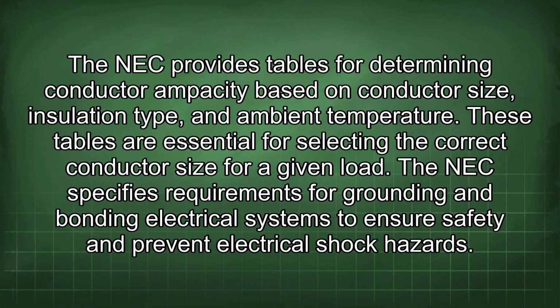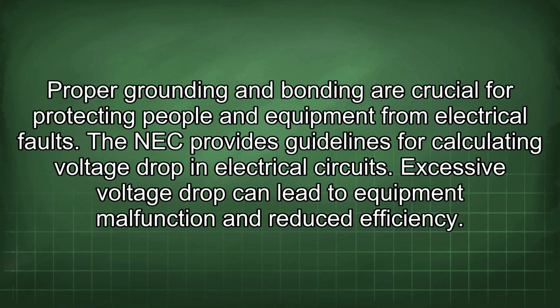The NEC provides tables for determining conductor ampacity based on conductor size, insulation type, and ambient temperature. These tables are essential for selecting the correct conductor size for a given load. The NEC specifies requirements for grounding and bonding electrical systems to ensure safety and prevent electrical shock hazards. Proper grounding and bonding are crucial for protecting people and equipment from electrical faults. The NEC provides guidelines for calculating voltage drop in electrical circuits. Excessive voltage drop can lead to equipment malfunction and reduced efficiency.